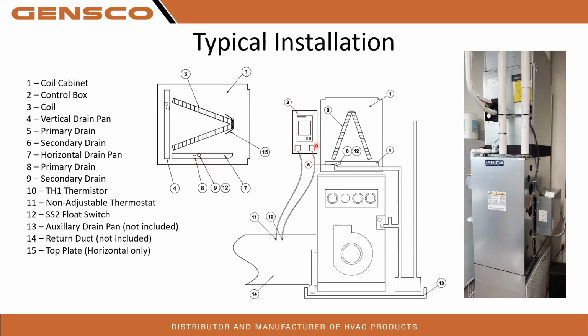Here is your control panel on the side of the coil, which is this right here. And you can see you've got your return temperature and your non-adjustable thermostat coming down into your return. It does not matter too much where in the return it is. If you have any kind of return heaters for any reason like that, or a zone system with a bypass, you will want to make sure that these thermistors are upstream of that so it does not affect the readings. You want a good accurate reading of the house.